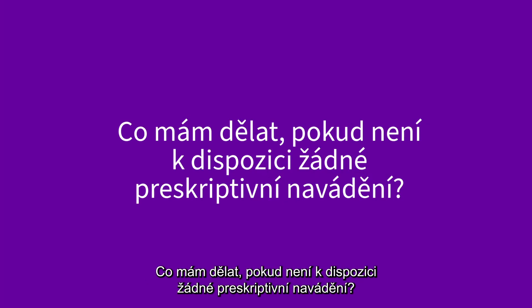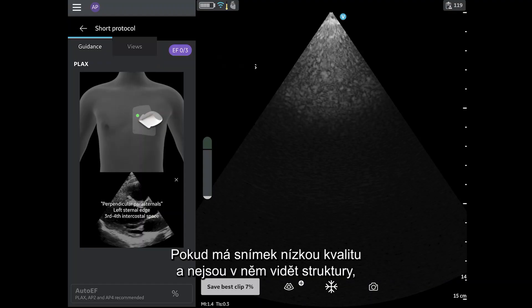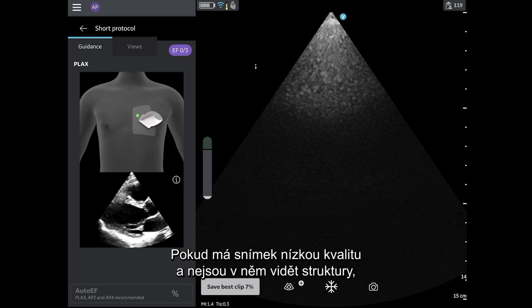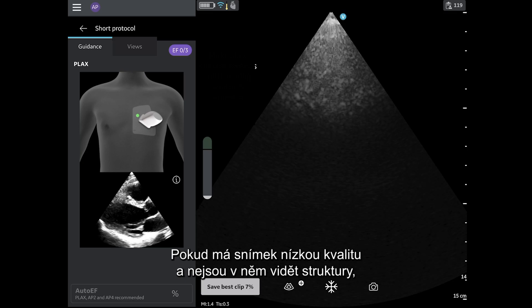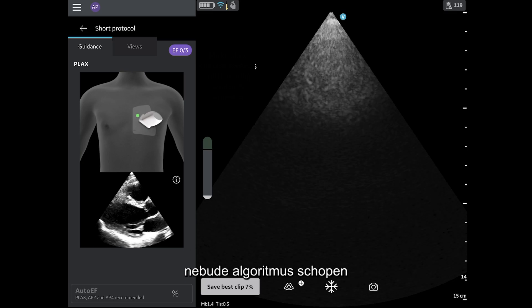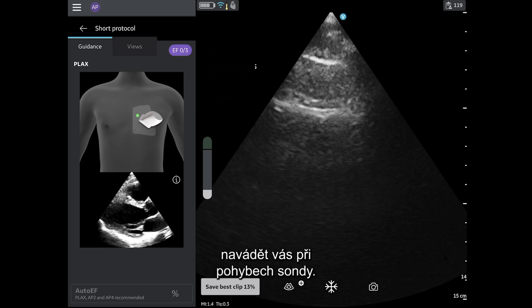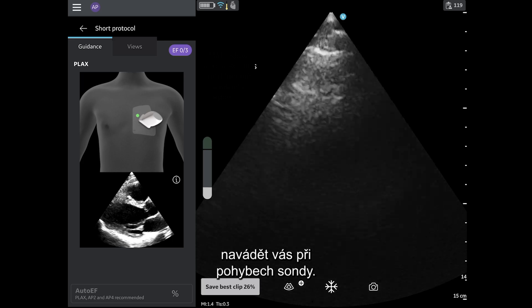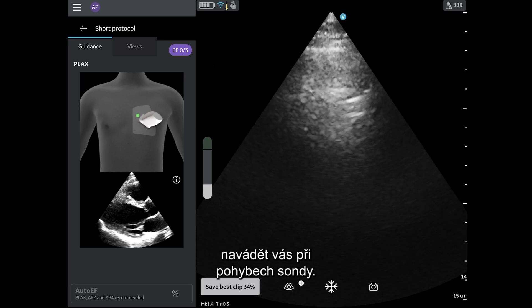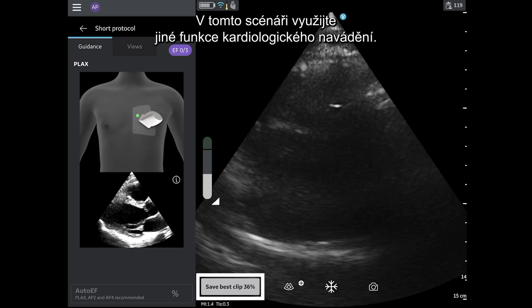What should I do if there is no prescriptive guidance? If the image is poor quality, without any structures visible, then the algorithm may not be able to provide any guidance for probe movements. In this scenario, rely on the other cardiac guidance features.